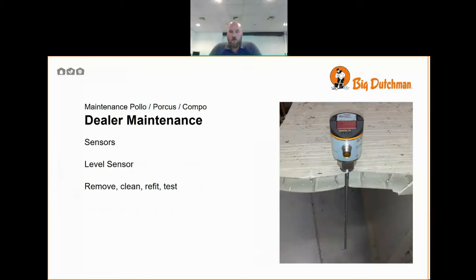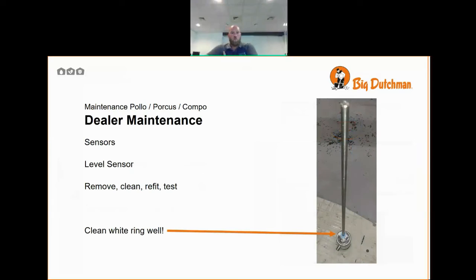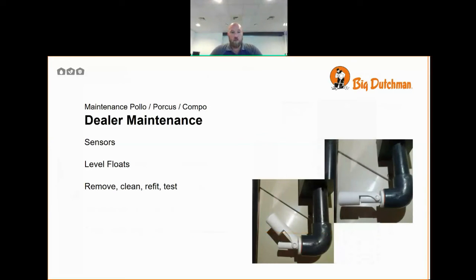The level sensor, the radar level sensor, you can see a cutaway where you can see through it here. This will become a little dirty over time. Although the filling water is shot at it and keeps it clean, it will need to be removed and cleaned. We need to make sure the white ring underneath is cleaned really well. This is where the radar is emitted from, and if there's any foam, dirt, muck clogging this white ring, it won't give a clear enough signal and will not read the water level correctly. The level floats, again, remove, clean, refit, and test.